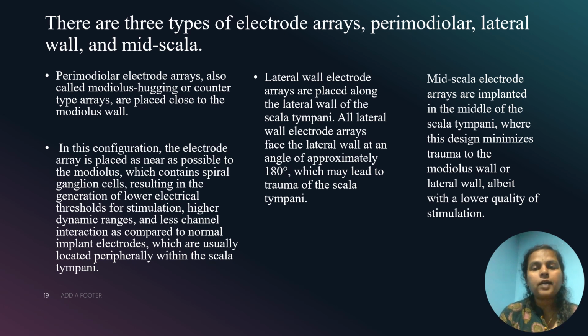And mid-scala electrode arrays are implanted in the middle of the scala tympani, where this design minimizes trauma to the modiolus wall or lateral wall, albeit with a lower quality of stimulation. So the perimodiolar type offers advantages over the lateral wall type in terms of lower stimulation levels, expanded dynamic range and better channel separation, because perimodiolar configuration provides a placement of electrodes closer to spiral ganglions than the lateral wall. So it leads to better neural stimulation, which may result in better speech perception.